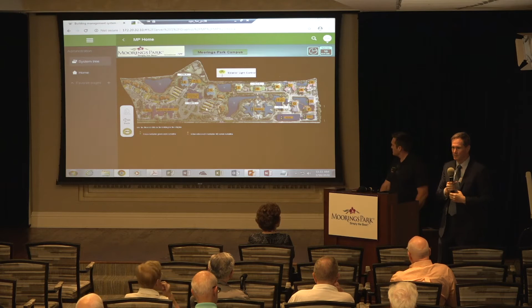Well, here's the lighting control to demonstrate how we can do it. Right now, it's tracking sunrise and sunset, and that will change every day. Down at the bottom, we've set up the commands for our clubhouse streetlights to come on 30 minutes before sunset and 45 minutes after sunrise. That will automatically adjust itself based on the clock it's pulling off the internet. So I don't have to go into the buildings at daylight savings, for example, and reset those old manual timers. It's done for me. Now, not all of our campus is set up this way, and we have a 5-year plan as part of our operations plan in our department to upgrade our controls over the next 5 years.